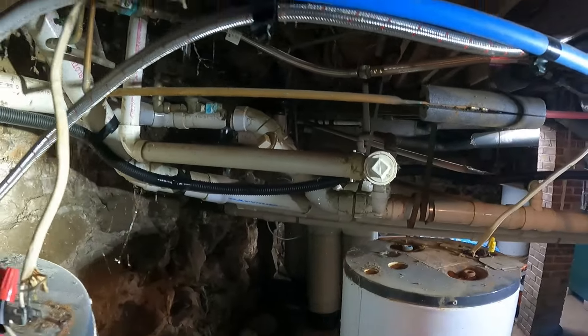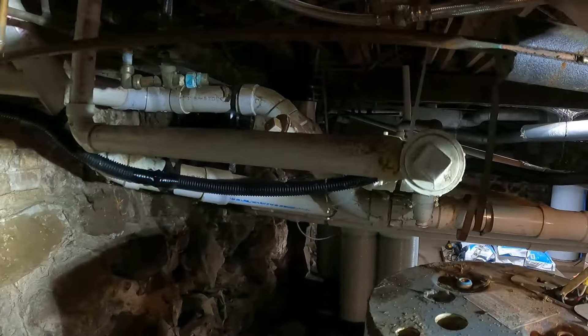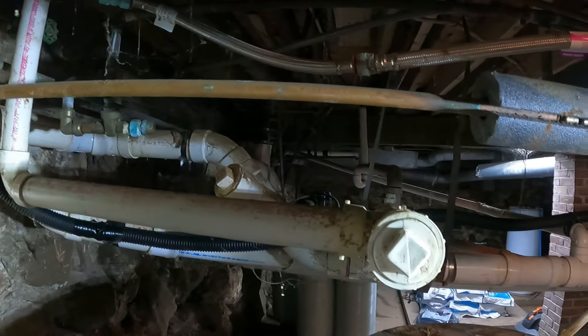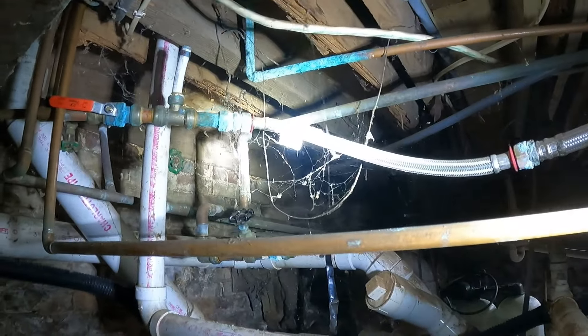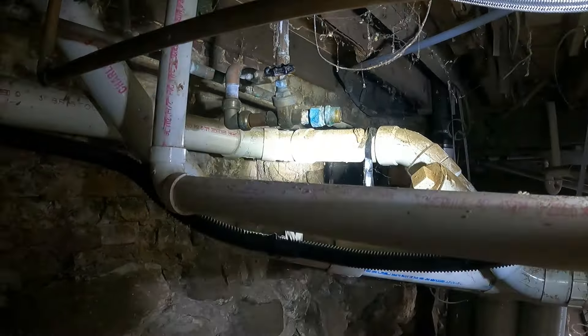What we've got to do is figure out — they've got the T and it's feeding that one tank feeding two apartments. But they've got a bunch of these hoses. Those braided hoses are made for hot water heaters, but I think they just put a bunch of those together. That one looks like a washing machine one — that would probably fail. None of these shutoff valves will show well over the flashlight, but all this green piping has got me a little bit nervous, to be honest with you. That shutoff isn't working — it's dripping water, so I've got to see if I can put a shutoff someplace else.